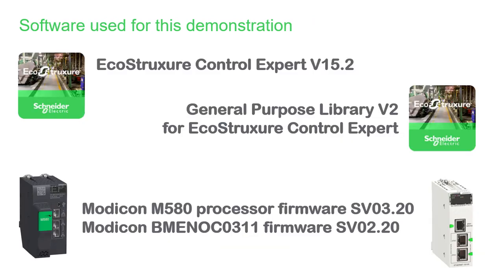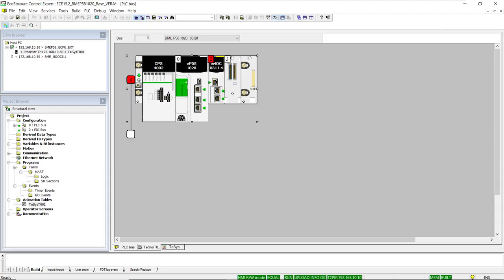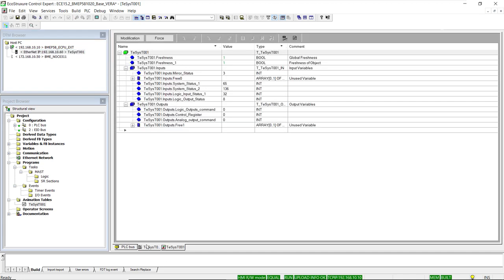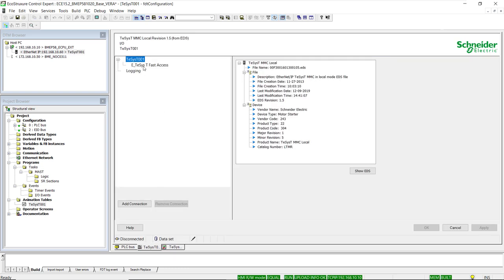For your reference, the software and firmware versions successfully tested for this demonstration are listed on this slide. Looking at the sample program prepared for the demonstration, this is an M580 PLC in which the CPU has a DTM object used to obtain data from a TeSys T motor controller using implicit Ethernet IP messaging, done by importing an EDS file that has a series of assemblies with predefined registers.